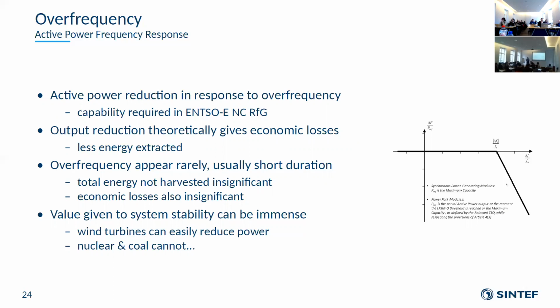But that's not really an issue, because it's short duration and very rare, so the total energy lost is tiny. But it gives real high value to the grid, reducing power in case of overfrequency. This is one of the things that didn't work in 2006, and that event would have been much smoother if all wind power plants had had this feature.